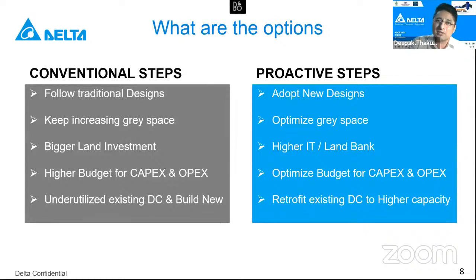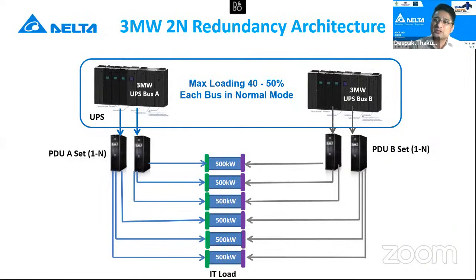So I'll give you an example here. Now let's talk about customers talking about their IT data hall capacities. I have come across 500 kilowatts, 1 megawatt, then 1.5, 1.6, 1.8, 2, 2.4, and 3 megawatts; the standard data hall is becoming a concept. And then you deploy multiples of them to meet your demand of 40 or 100 or 200 megawatts. So what is the conventional way of doing it? The conventional way was to replicate and mirror.